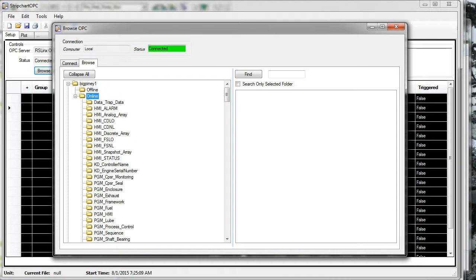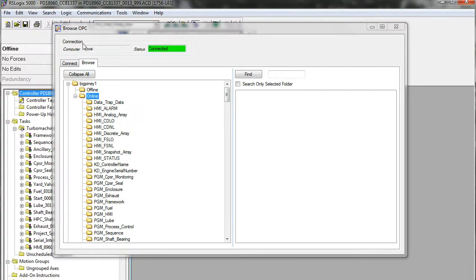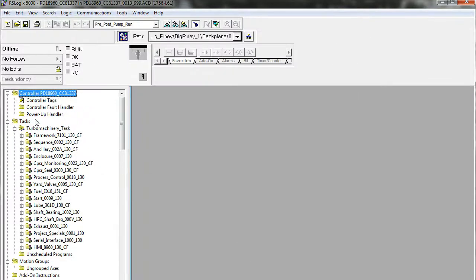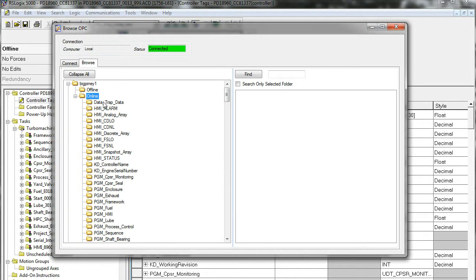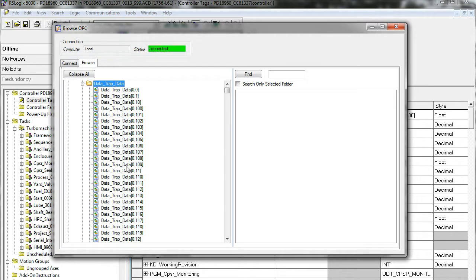I've browsed online and looked at the data structure in that processor. Let's look at the processor now — here's the ACD file. What I'm looking at first is the data structure in the controller scope data. I've opened the controller tags, and the first entry I see is a matrix of reals called 'data trap data.' Browsing StripChart, I see a folder called 'data trap data.' Opening that folder browses into that matrix and shows each element. When you see this icon appearing different than a folder, that is an actual PLC address with a real value that you could trend in StripChart OPC.